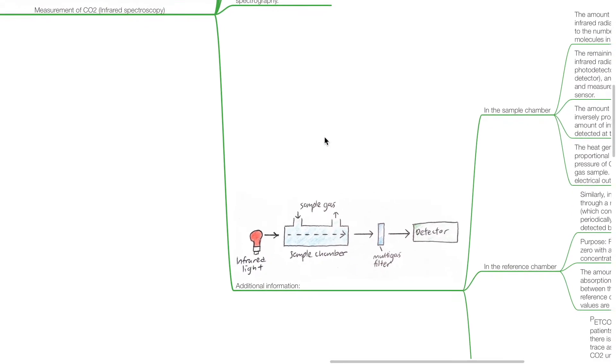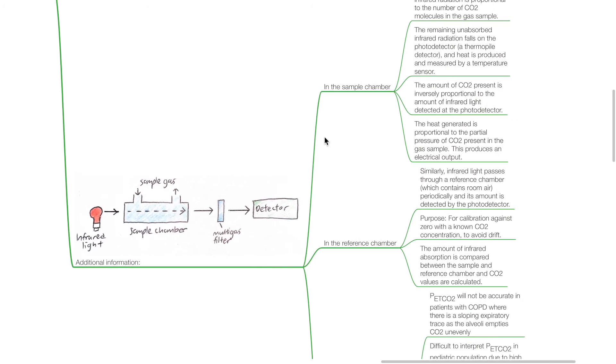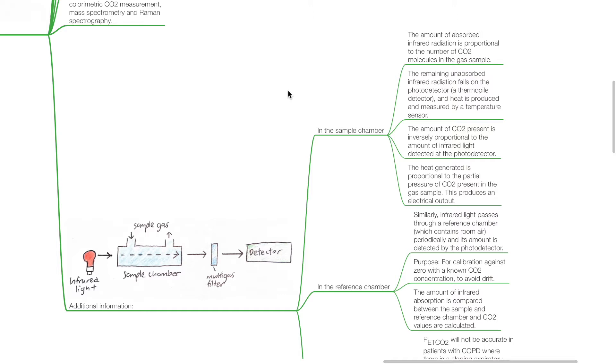Additional information: In a sampling chamber, the amount of absorbed infrared radiation is proportional to the number of CO2 molecules in the gas sample. The remaining unabsorbed infrared radiation falls on the photodetector, which is a thermopile detector, and heat is produced and measured by a temperature sensor.